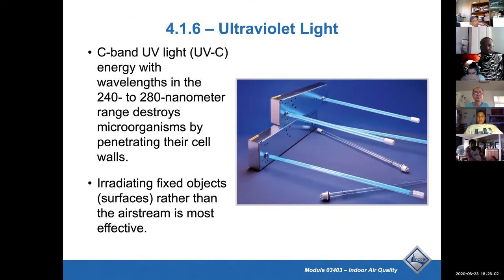Okay, UV lights. This is a new thing, right? New UV lights. They've been around for the last 10 years. The only thing I know about UV lights negative is you shouldn't be using it in a plastic environment, like an air handler that has plastic inside, like a mini split, because it weakens the plastic. Also, UV light's not good if you look at it directly, right? So you need to have it turned off when you're servicing it. And another thing about UV light, it only treats what the light shines on. So if you have a corner that goes around where you don't have a UV light, it's not going to irradiate that.